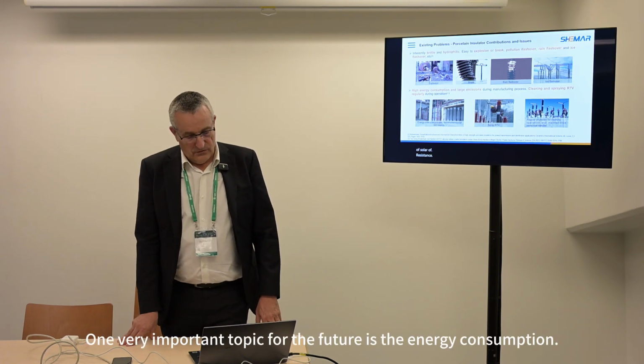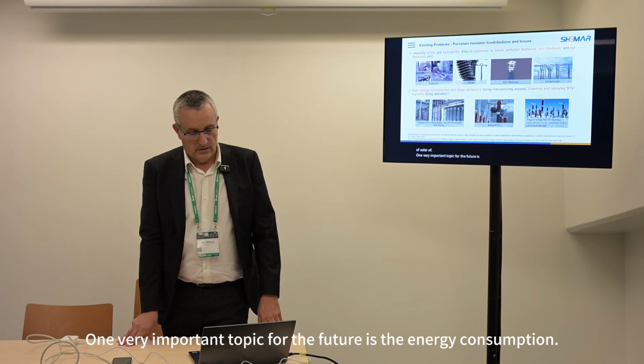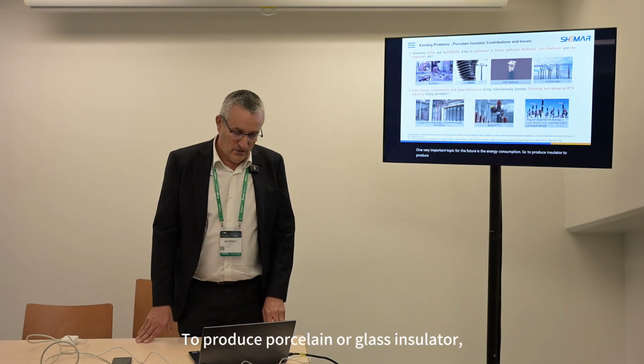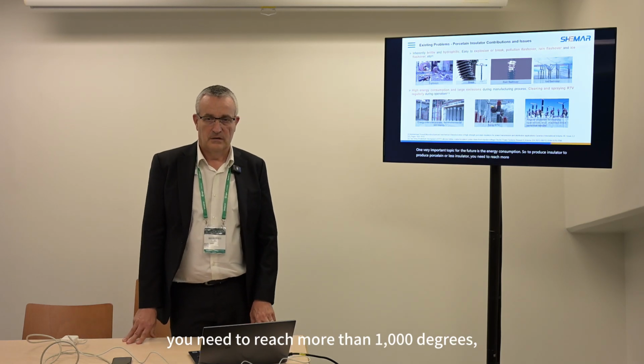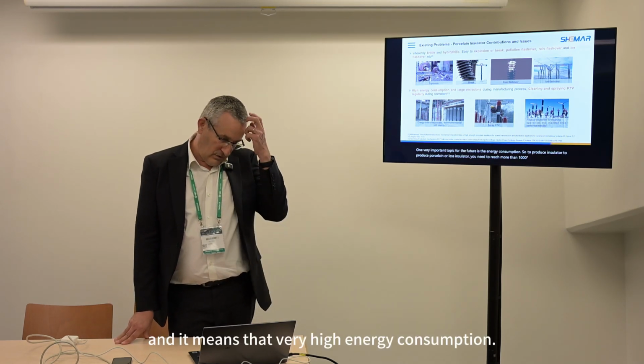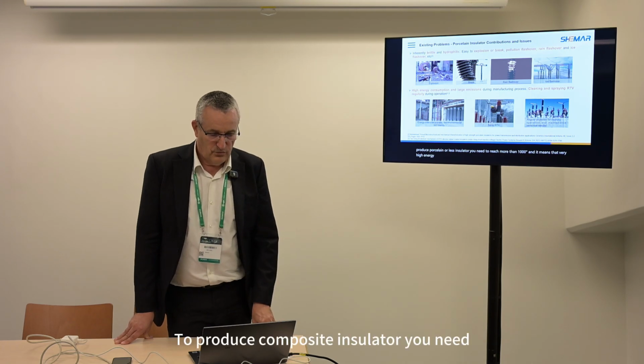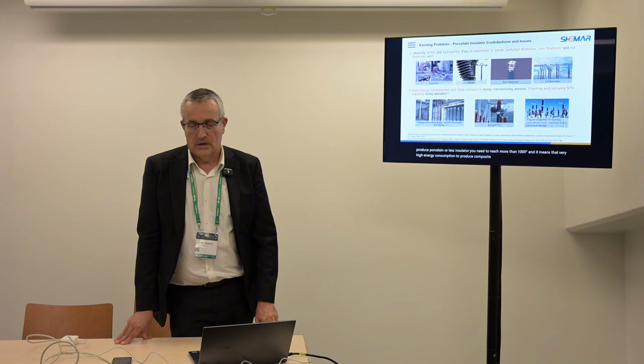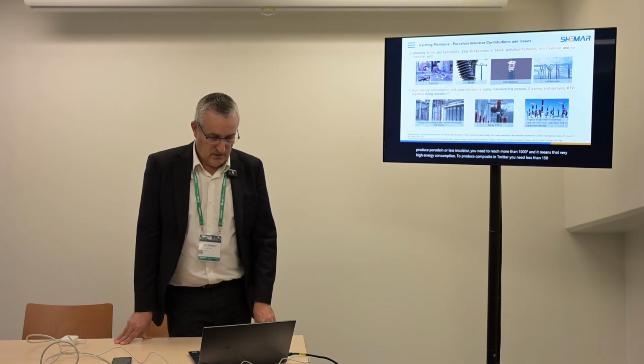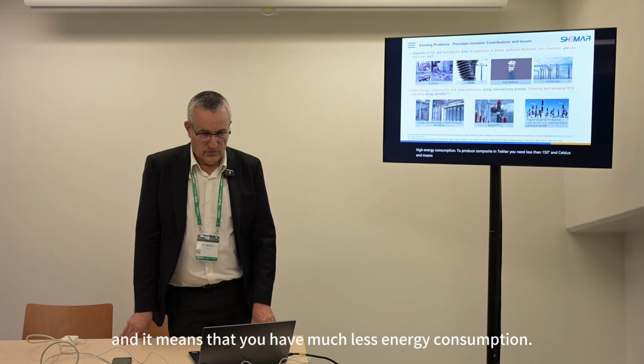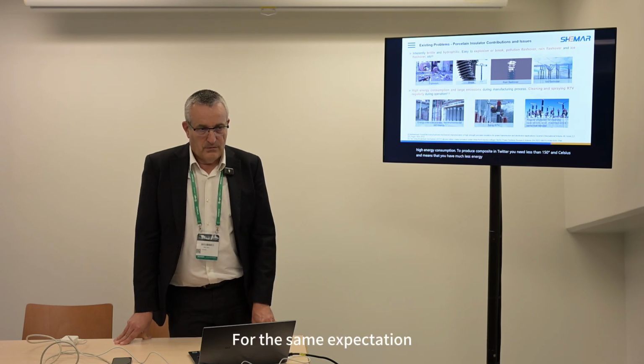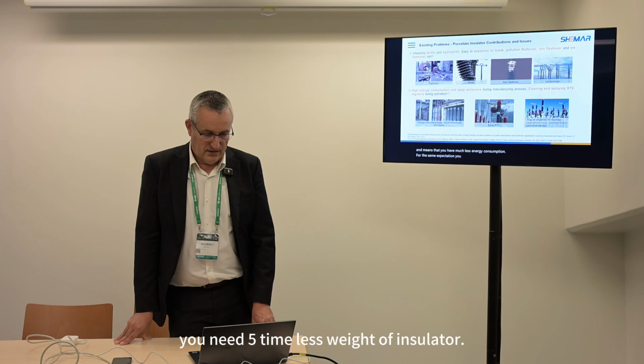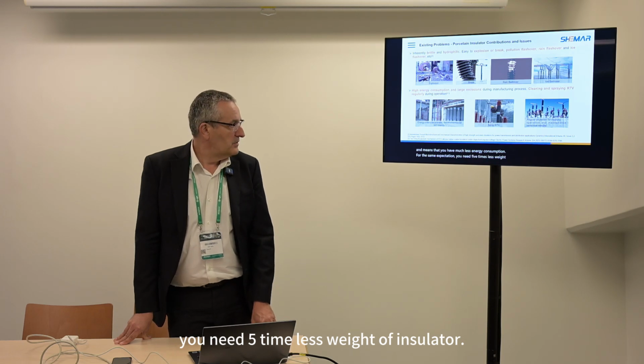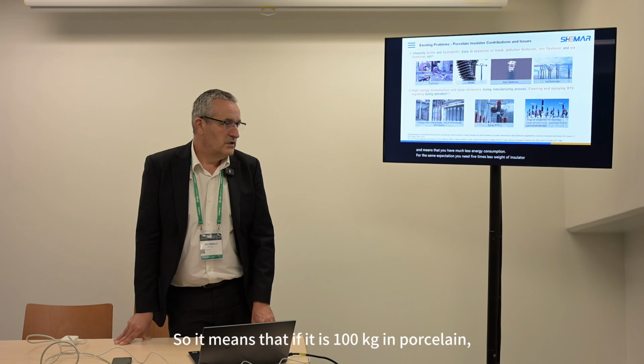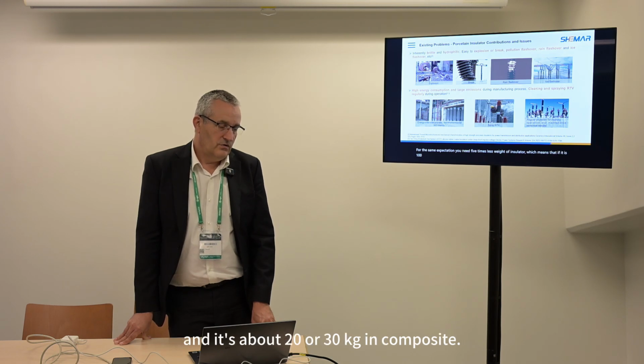One very important topic for the future is energy consumption. To produce porcelain or glass insulators, you need to reach more than 1000 degrees, which means very high energy consumption. To produce composite insulators, you need less than 150 degrees, which means much less energy consumption. For the same expectation, you need 5 times less weight of insulator. So if it is 100 kilos in porcelain, it's about 20 or 30 kilograms in composite.